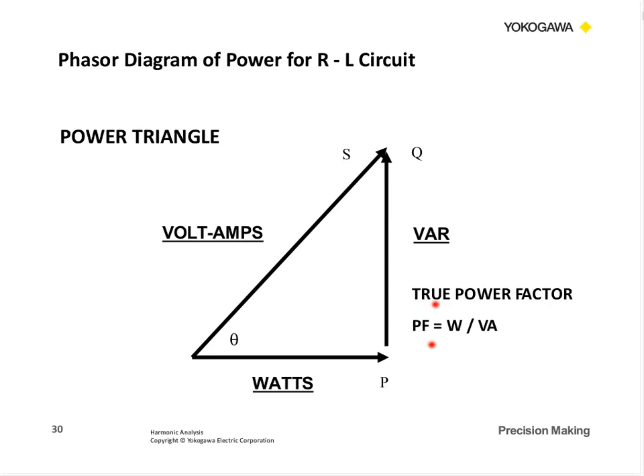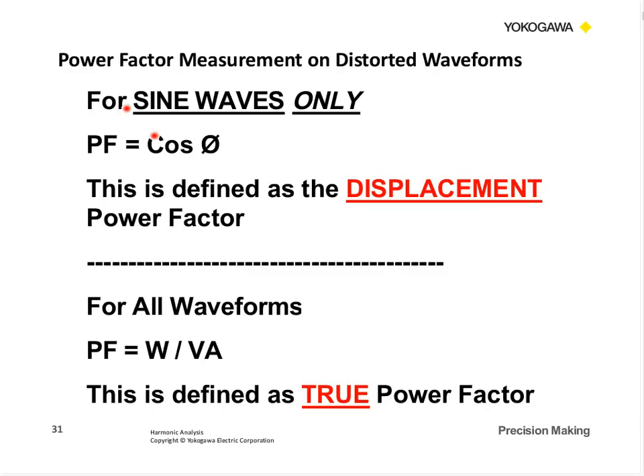And this is true power factor. So for a sine wave only, we can use power factor equal to cosine of theta, and we can get a good zero crossing and measure that time and get the angle. This is what is defined as displacement power factor. But for all other waveforms and what we typically deal with in our day-to-day work, we don't have nice clean sine waves, and so that's where we do the watts divided by VA, and this is defined as true power factor. So regardless of what the waveforms look like, you saw how we calculate the watts and the VA. Doesn't make any difference. These are true measurement values. So this is the true power factor.